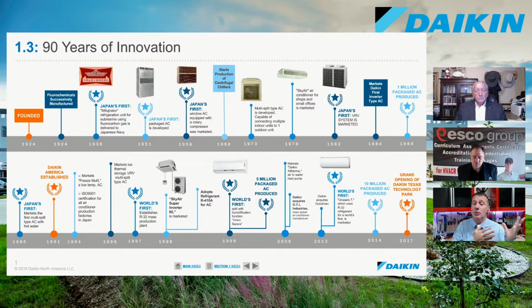So we teach the fundamentals, we do it with mechanical gauges and with thermometers, then show that we do the same with our digital gauges. Now think about these inverters, they're driven by pressure transducers and temperature thermistors already built into the equipment. So we have so much onboard diagnostic capability that we just don't have with a traditional piece of equipment. If we could teach the fundamentals of why we're reading superheat and subcooling, then move into what our tools are actually doing, and then onto equipment that already has it on board, understanding that entire development from mechanical to digital to implementation means the equipment itself is going to make more sense.